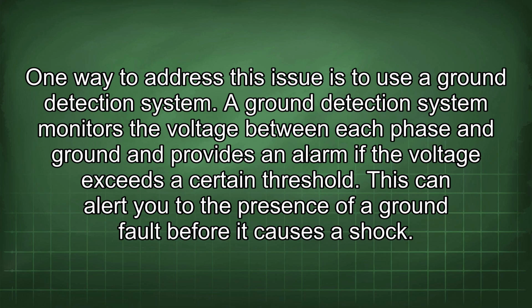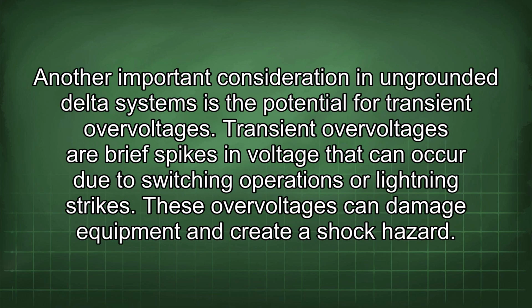A ground detection system monitors the voltage between each phase and ground and provides an alarm if the voltage exceeds a certain threshold. This can alert you to the presence of a ground fault before it causes a shock. Another important consideration in ungrounded delta systems is the potential for transient overvoltages. Transient overvoltages are brief spikes in voltage that can occur due to switching operations or lightning strikes. These overvoltages can damage equipment and create a shock hazard.